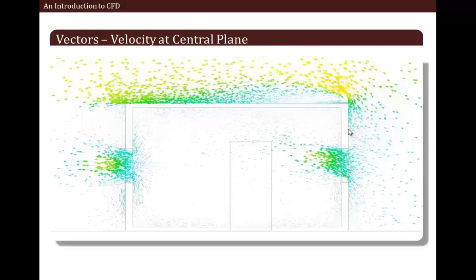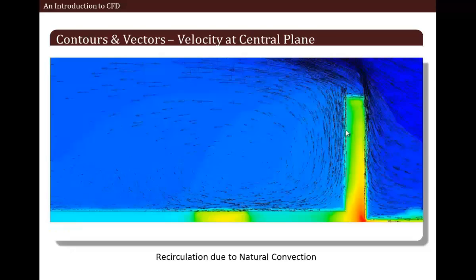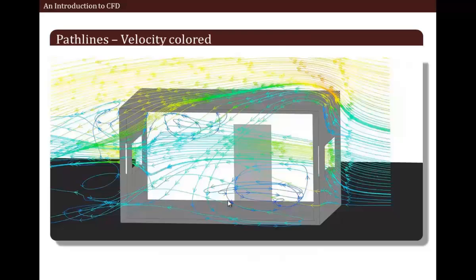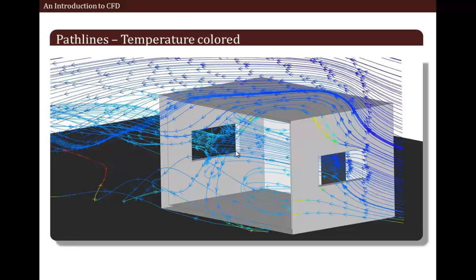Now let's see a few vector plots — this is a velocity plot colored by velocity magnitude. Here we have a combination of vectors and contours both based on velocity magnitude. In this picture we can see the flow circulation caused by natural convection. The solar loading effects of the sun rays coming from the window are clearly visible. Now let's see a few path lines — here we can see the flow distribution with velocity-colored path lines. In the next one, we see temperature-colored path lines. It is clearly visible that air at ambient temperature is entering the room but gets heated up due to solar loading and exits the room with a higher temperature.